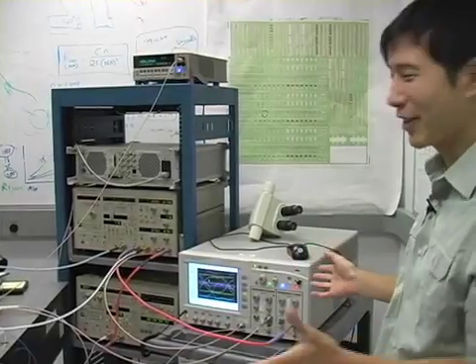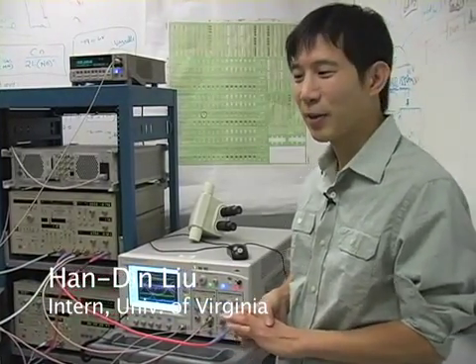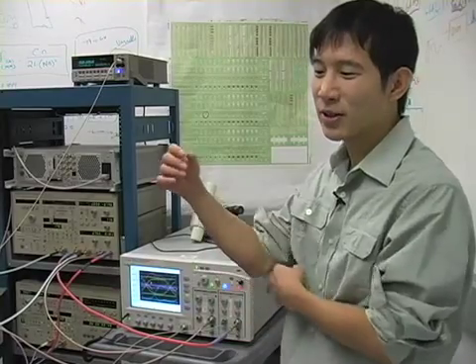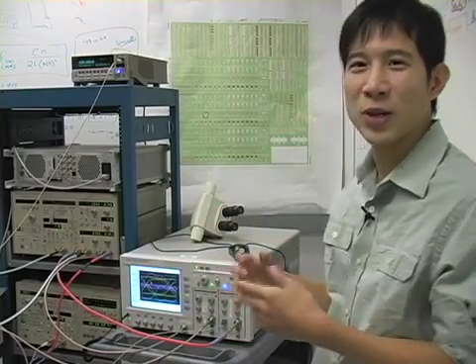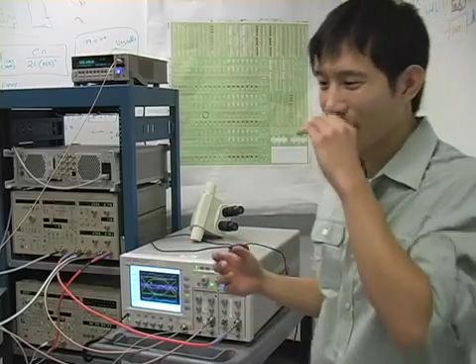This setup we have here measures the sensitivity of avalanche photodetectors. Basically, what this measurement means is how weak you can tune the optical signal and still detect what the signal is.